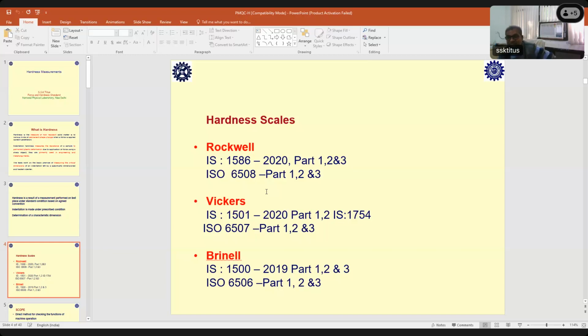And part 3 talks about the calibration machines. It is one step advanced compared to part 2. Part 3 talks about how standard hardness blocks can be calibrated. What is the requirement for the kind of machine that should be used for calibrating the standard hardness block? Because a standard hardness block is going to be a kind of reference material for calibrating all the testing machines across the country, the calibration machines have very tight specifications. What kind of indenters, what the geometry and its tolerance should be, what the force and its tolerance should be, and what type of timing cycle one has to maintain.